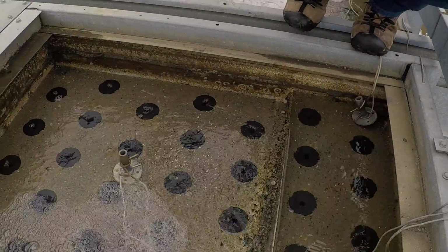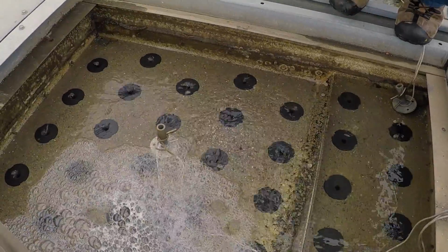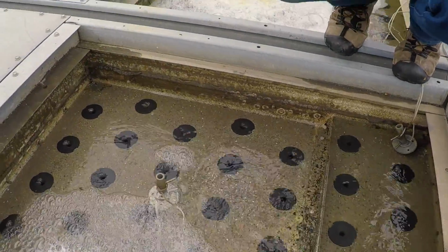A real fast way in the field to tell if the tower flow is balanced, and if you haven't gotten it at this point but watching these strings of videos, when you go look at the towers, pull the basin covers. You want to know that, right? Well, if you want to figure out if the flow is balanced, if they're identical cells with identical nozzles with identical orifices, if the flow is balanced, the water level in every single basin will be the same depth.